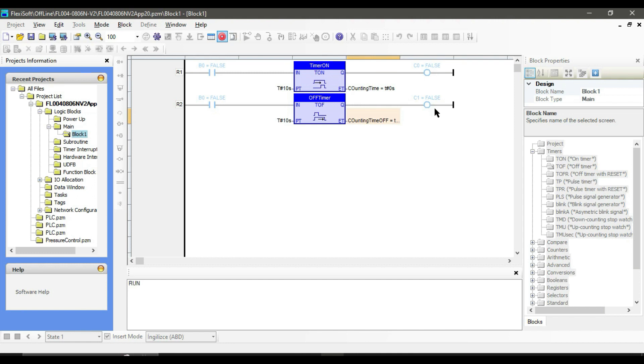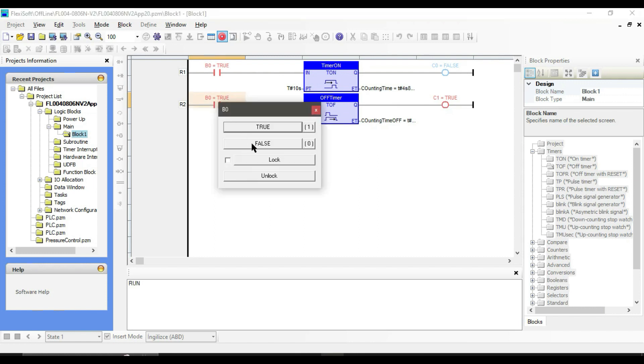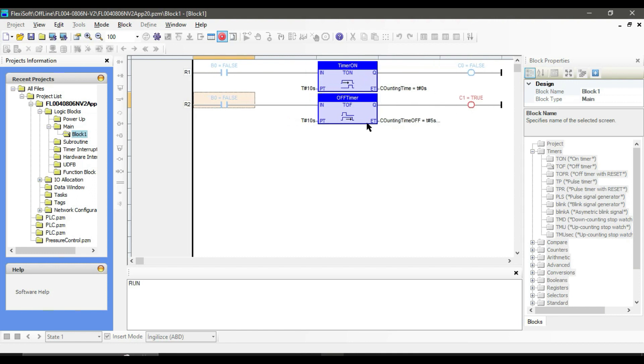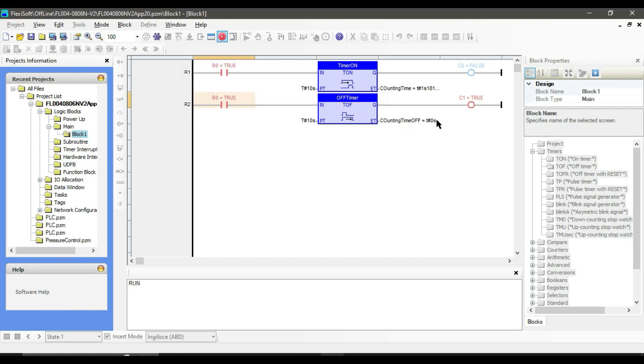As soon as we make the input true, the output will also be true. If we turn off the input, the output will stay true until the elapsed time reaches the preset time. Remember that the output will not become false if we turn on the input before the elapsed time reaches the preset time.